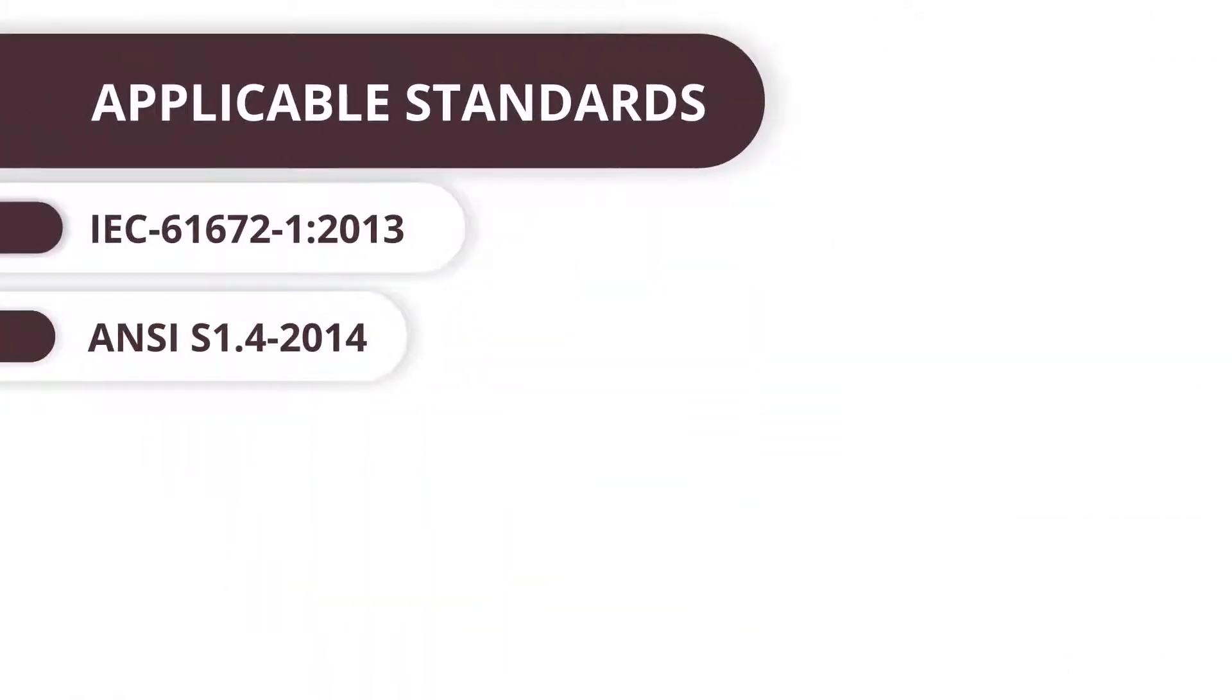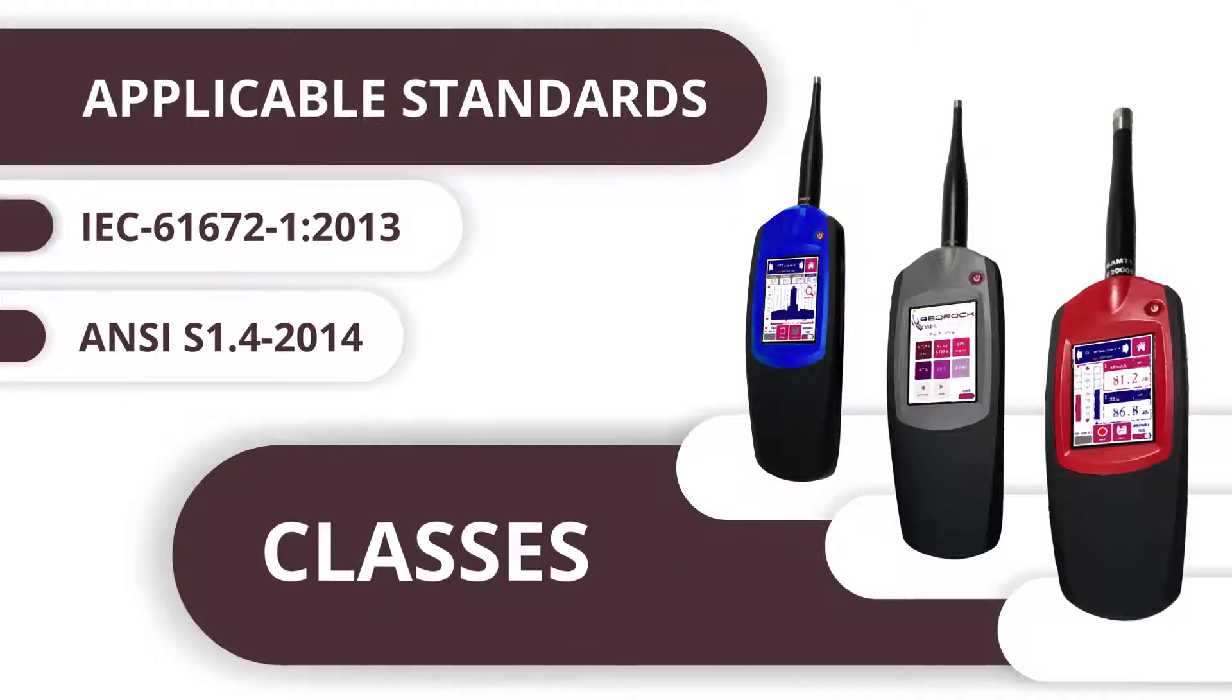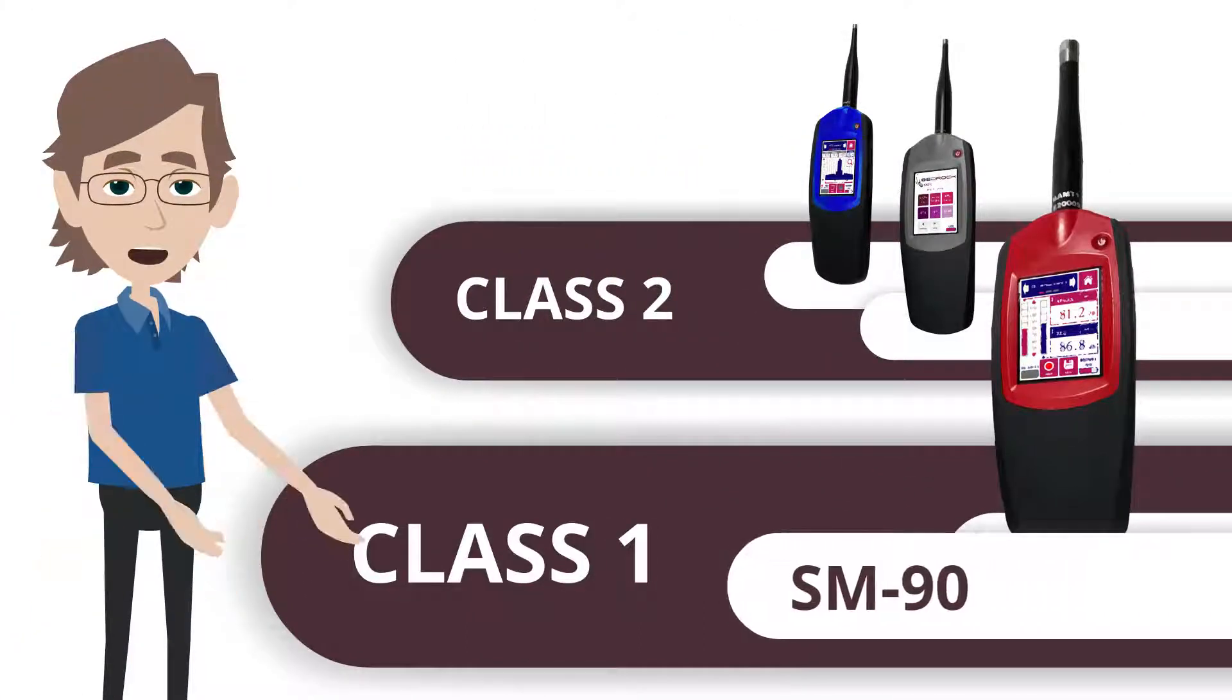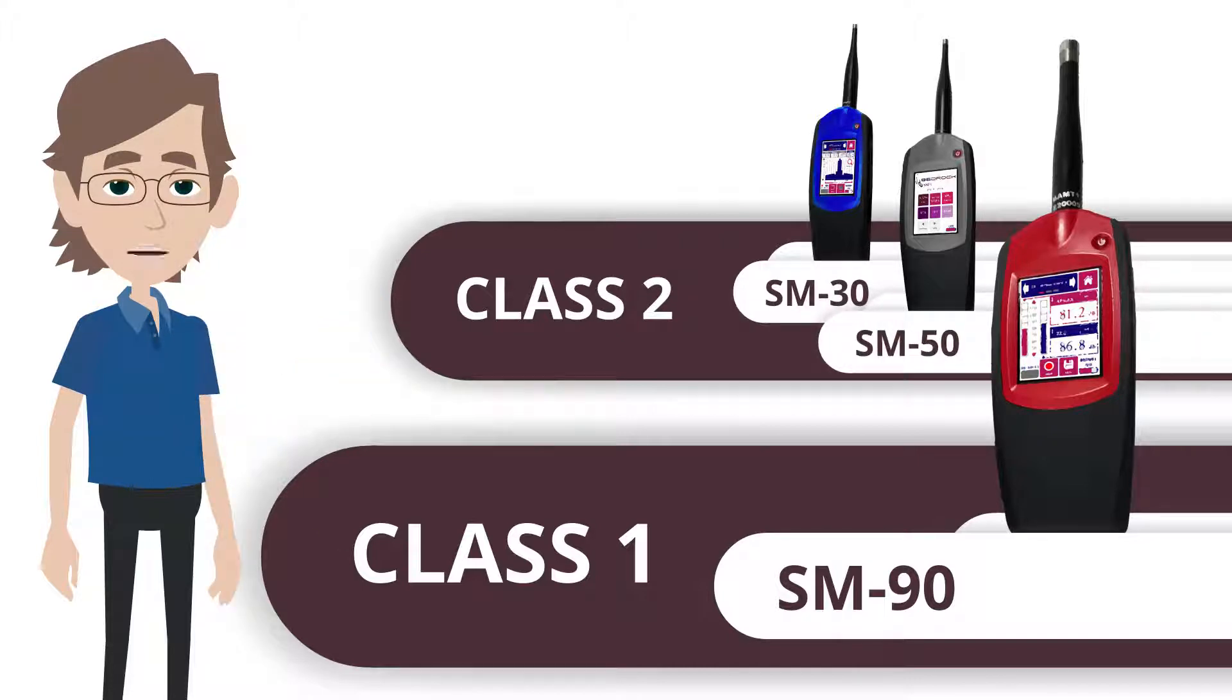According to the applicable standards, sound level meters are categorized into classes depending on various factors that relate to measurement accuracy. The Bedrock SM90 complies with Class 1, the highest categorization. The Bedrock SM30 and SM50 fall into Class 2.